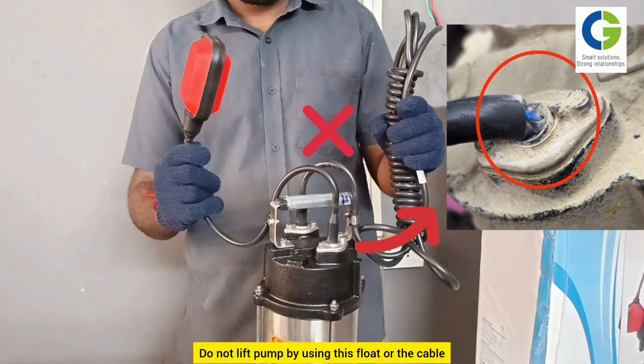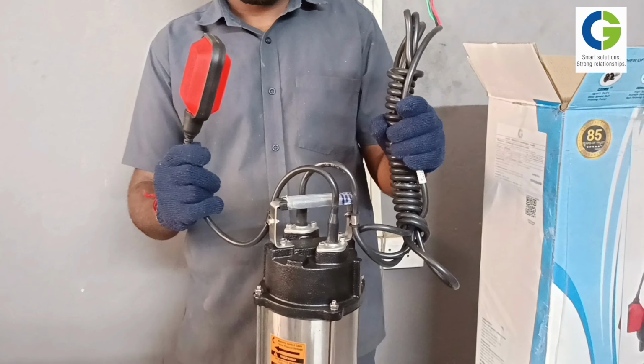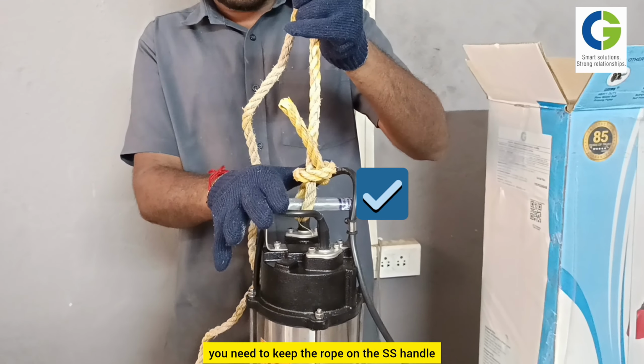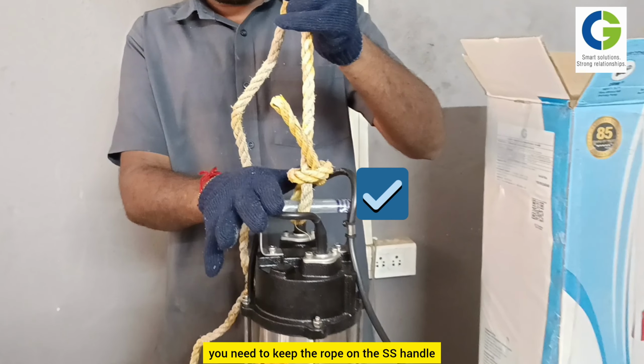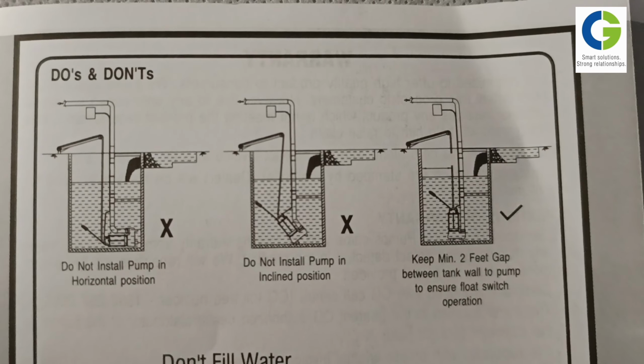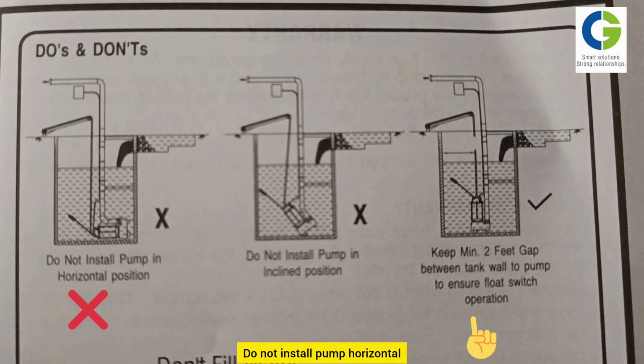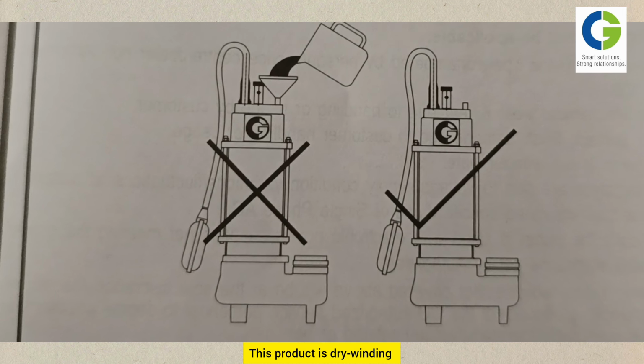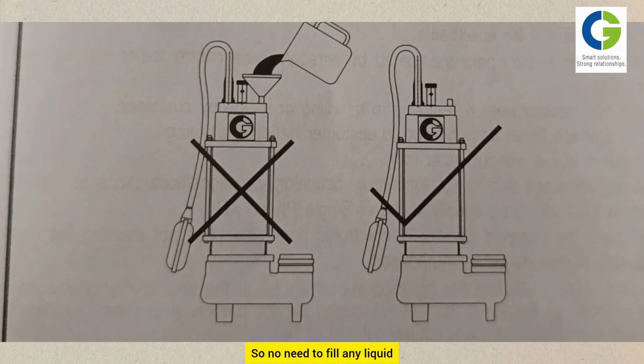Do not lift the pump by using the float or the cable. You need to keep the rope on the SS handle. Don't tie any float switch or cable on the rope. It will damage the cable in this place. The pump should be mounted vertically. Do not install the pump horizontally or in any inclined position. This product is dry wound, so there is no need to fill any liquid or coolant inside the pump.